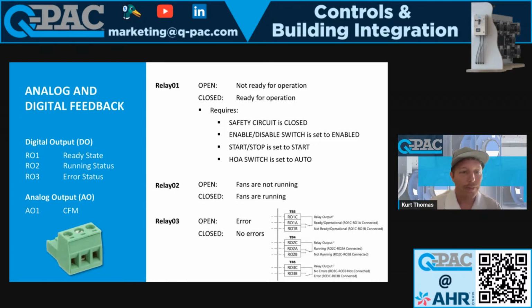He's probably bored, but RO1, ready state. So just saying, hey, your fan array is ready and operational. It doesn't necessarily mean that your fans are running. It's just saying, hey, your safety circuit is closed, your enable disable switch is enabled, start stop is in start, and your HOA switch is set in auto. So your fans are ready to operate and they may be operating.